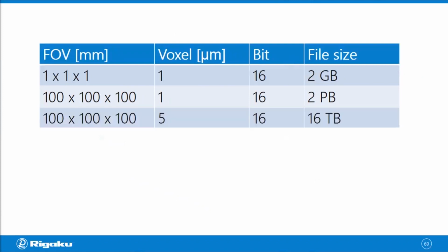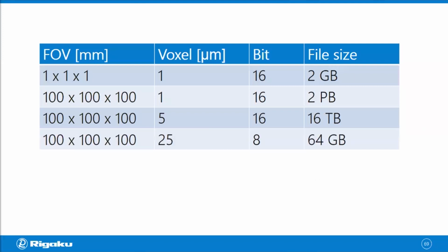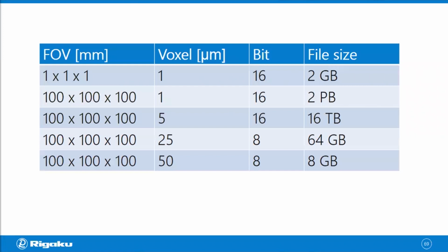If you go to 5 microns, it's 16 terabytes, probably still too big. You go to 25 microns, maybe 8-bit for grayscale, it's 64 gigabytes. Now you can probably save this on the drive, no problem, but you might have a hard time analyzing it. So 50 microns voxel size is probably more reasonable. Your file size is now 8 gigabytes. As you can see from this table, you have to compromise on the resolution and use larger voxel size when your FOV becomes large, just to keep the file size under control.